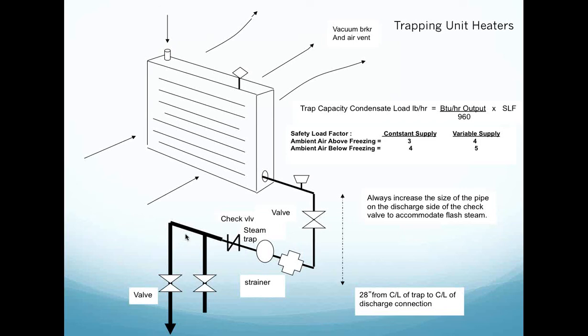You'll see an air vent on the top of this unit heater. You'll see a vacuum breaker on the discharge line. When we consume the enthalpy, the BTUs per pound out of that steam, we're going to collapse that steam and potentially create a vacuum in that space. The vacuum breaker helps us. If this steam system goes down on this unit heater, it will end up seeing a vacuum. That vacuum will hold that condensate inside that coil. If you have a platen press, if you have a dry kiln coil, if you have any kind of a blast coil or coil heating dryer, I need you to know when that system goes down, if you don't have vacuum breakers installed, it will be very difficult to evacuate that condensate that's being formed.